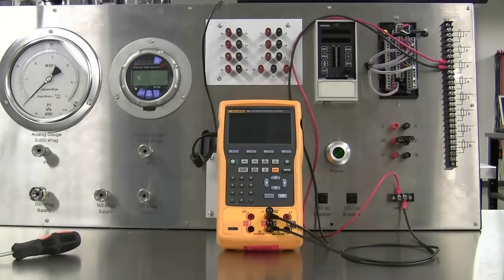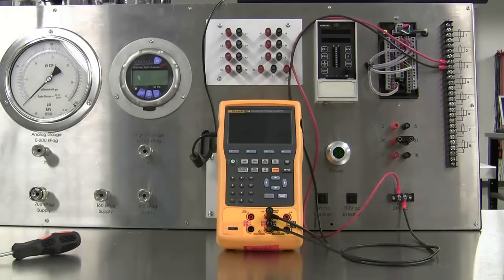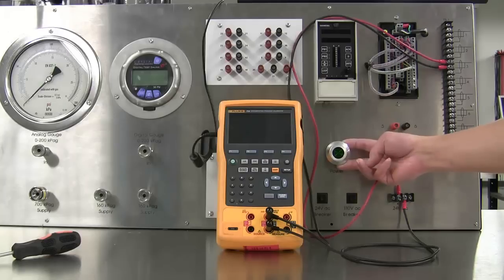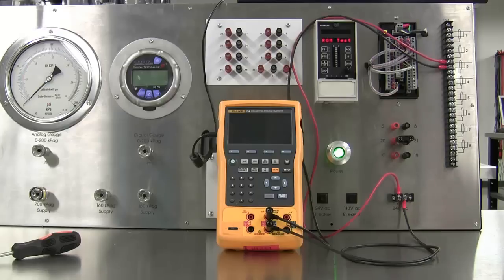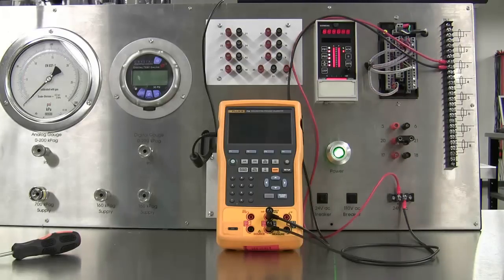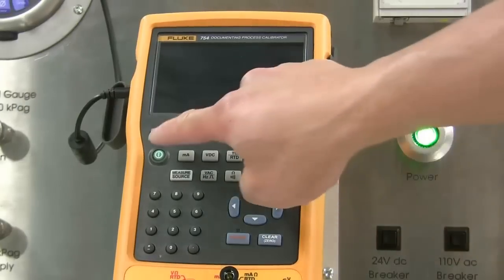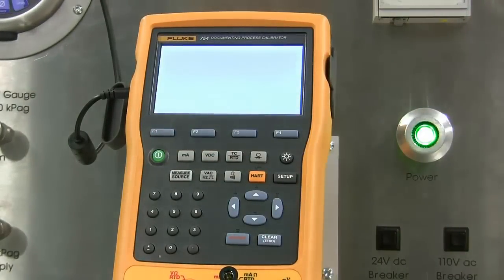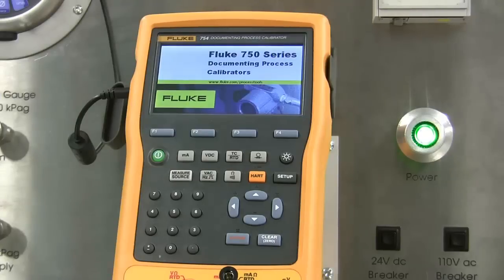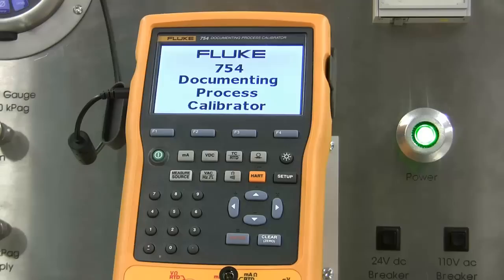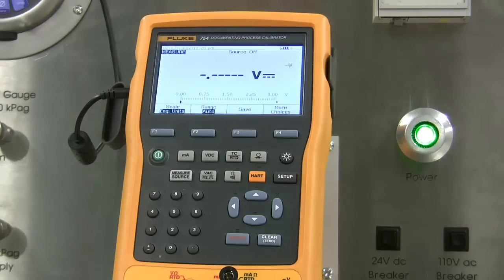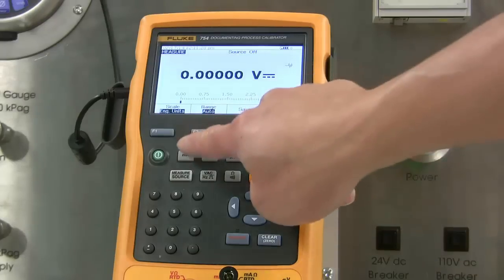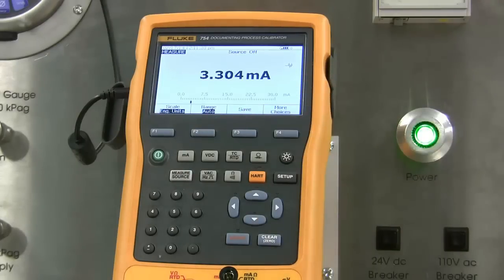You can go ahead and power on the transmitter. Turn on the Fluke and set the Fluke to measure milliamps. If you wired up the transmitter properly, you should see about 4 milliamps showing on the Fluke.